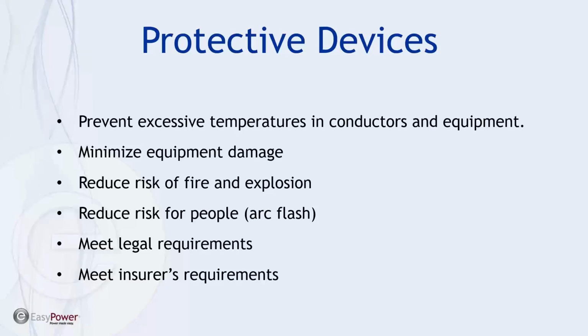So protective devices have a number of particular functions in system design. First and foremost, they protect the equipment from excessive temperatures and excessively high loads or faults to minimize equipment damage. They often reduce the risk of fire and explosion and potentially reduce the risk to personnel. Often it's required as part of a legal document, specifically the code, when we talk about commissioning a plant or a new facility. And then frequently it can be part of an insurance coverage issue, to make sure that you have the proper devices in place to protect the equipment.